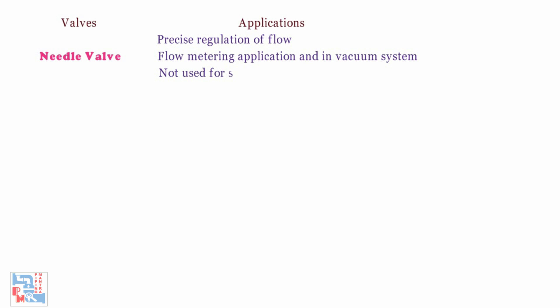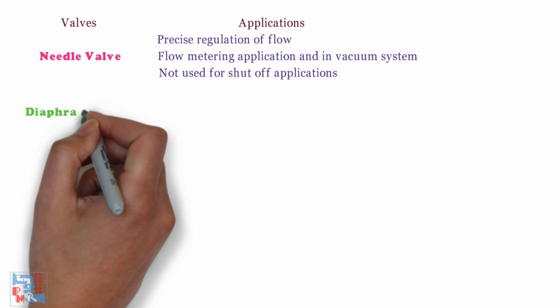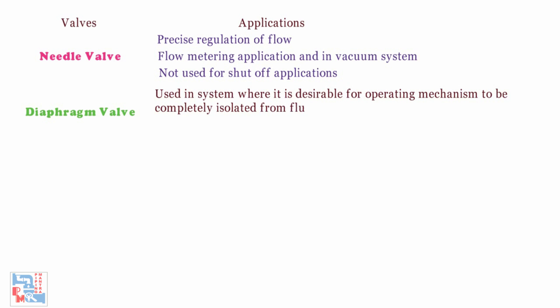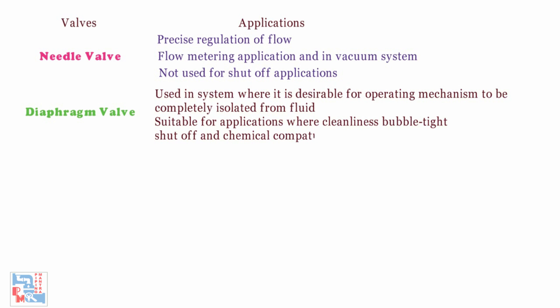It is not used for simple shut off applications. Diaphragm valve. It is used in systems where it is desirable for operating mechanisms to be completely isolated from fluid. It is suitable for applications where cleanliness, bubble tight shut off and chemical compatibility are important.